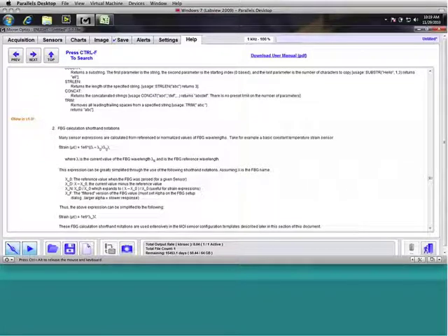And then this X_normalized, X_N, implies a normalized sensor, which is that delta sensor over the reference sensor, which of course expands to the current minus the reference over the reference. And so this whole expression that we start up here can really be simplified down to this one expression of lambda_normalized. And as Dan said, really what this does in many cases is allows you to enter that expression into a create sensor window so that it really resembles the sensor information sheet or the published expression for that particular optical sensor.